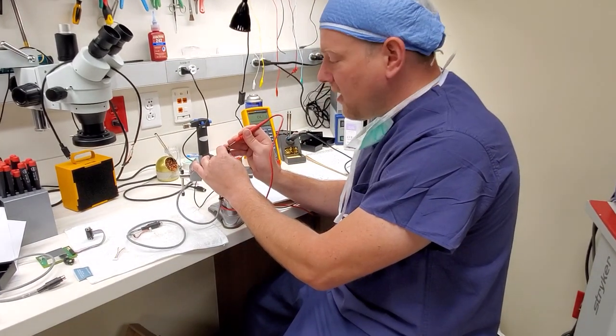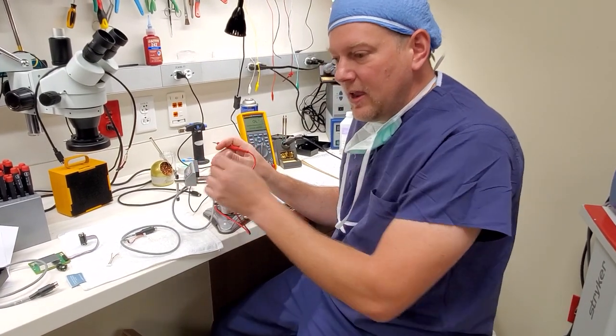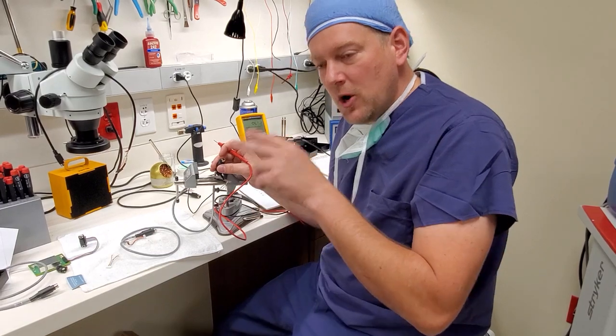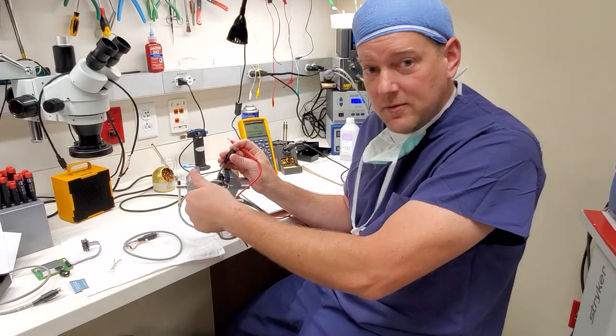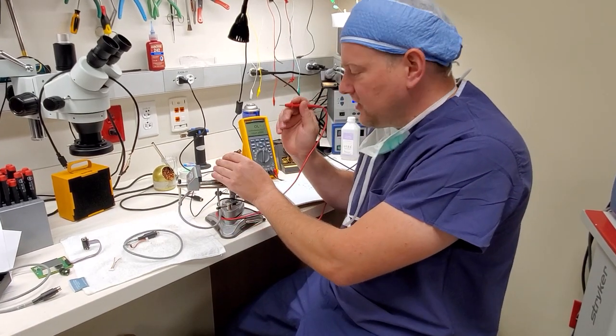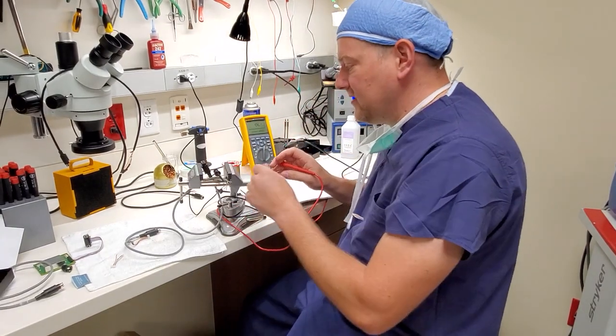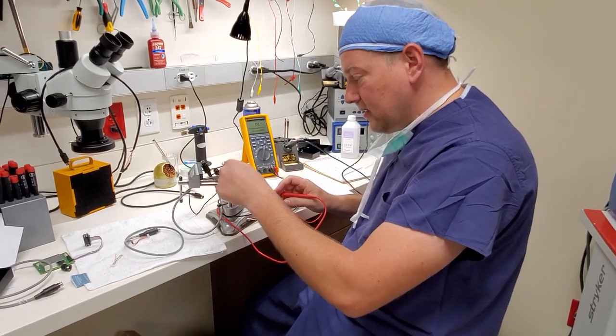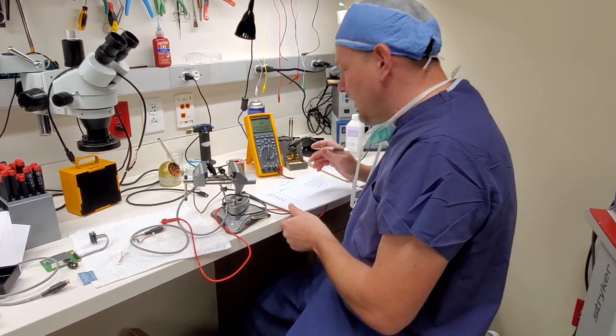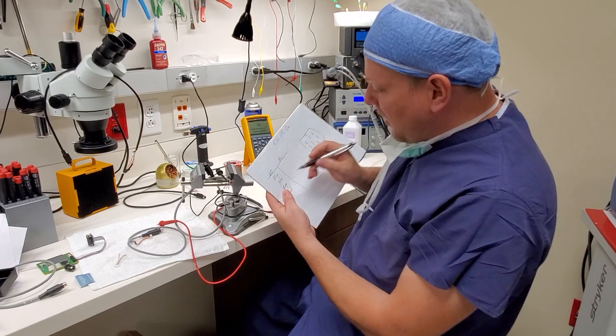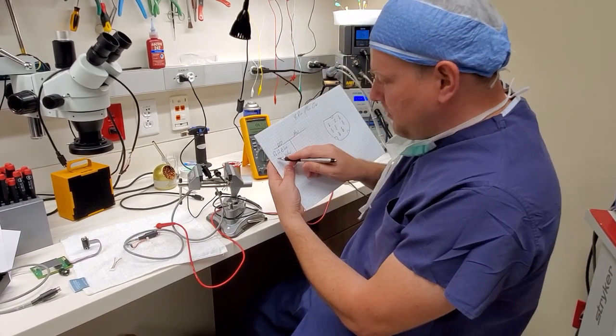Now you got to check the other pins because in some cables you will have a resistor or a jumper either inside the connector, on the back of the connector, or in line down the cable someplace. So be sure to check your cable to make sure that there's only one pin that is continuous to that specific wire. So then I'm going to take my ink pen. That was pin 2. So I'm going to write pin 2. Pin 2 blue.